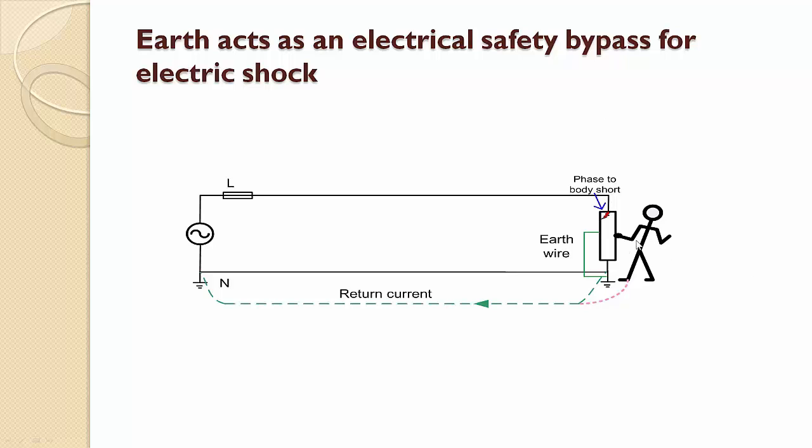So to avoid that, what I have done is I have bypassed, or I have connected an earth wire. That is bonded securely to the metal part of this equipment. And I have earthed that to the earth terminal here. So what happens is, even if there is a phase-to-body fault, the current will pass through the earth wire. And it will complete its path by passing the guy. It will complete its path and return to the source.